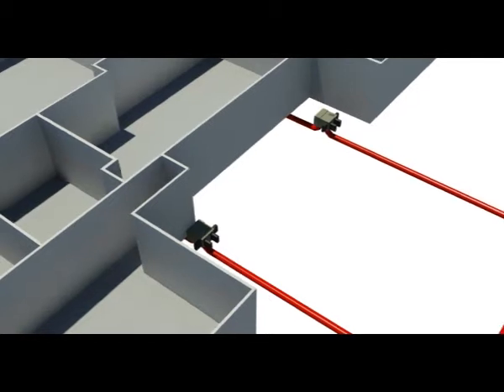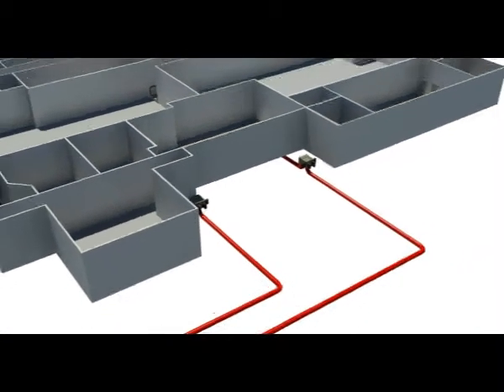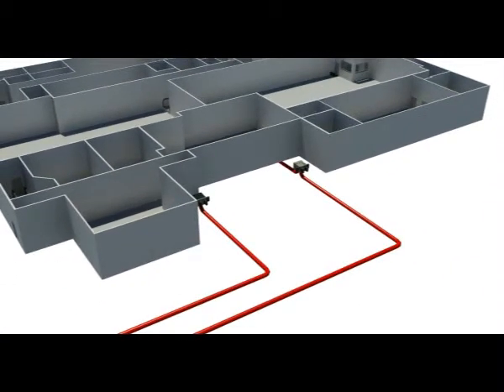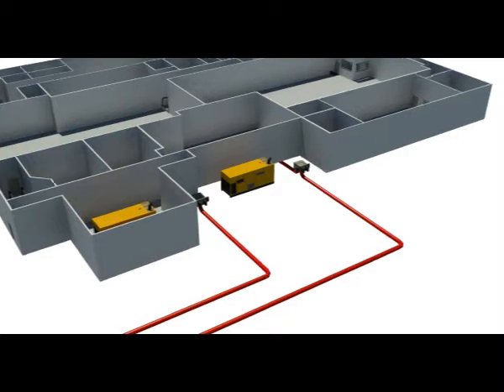In the unlikely circumstance that commercial power from both feeds to the site are temporarily disabled, these systems are supplemented by 3 generators, one 1,000 kilowatt with a 1,000-gallon diesel fuel tank, and 2 800-kilowatt Caterpillar diesel generators, and 5,000 gallons of diesel fuel on site, which can power the center for as long as needed.